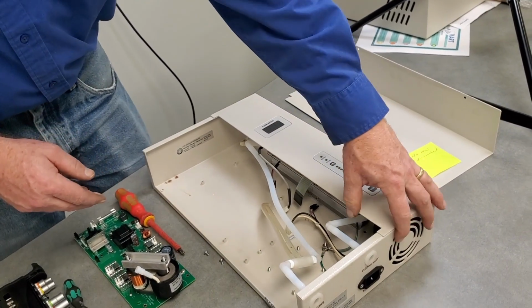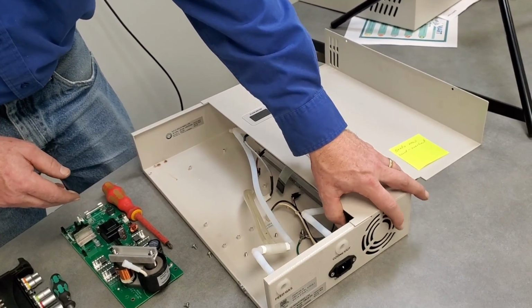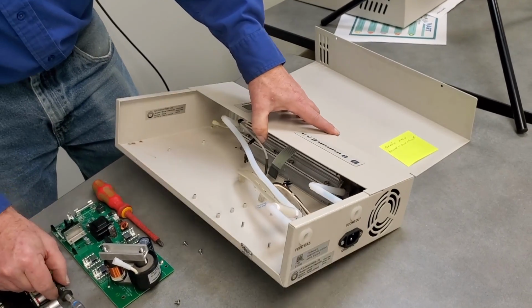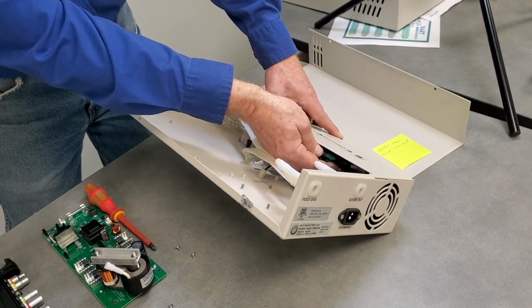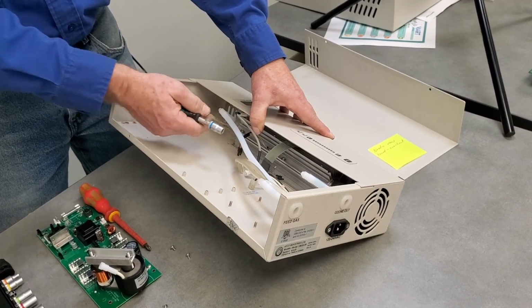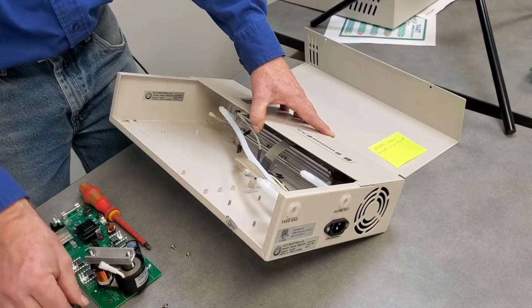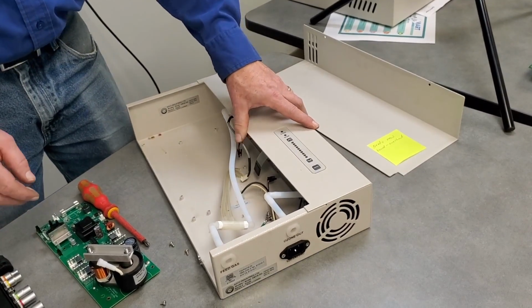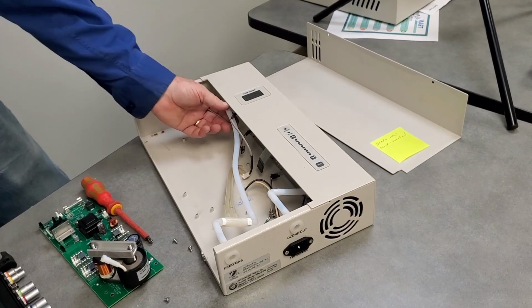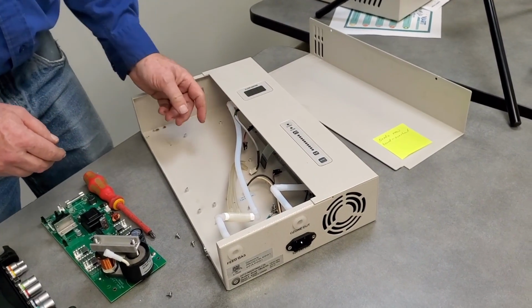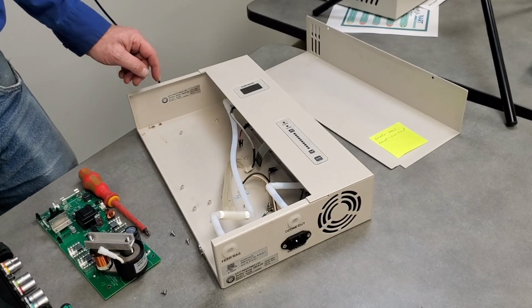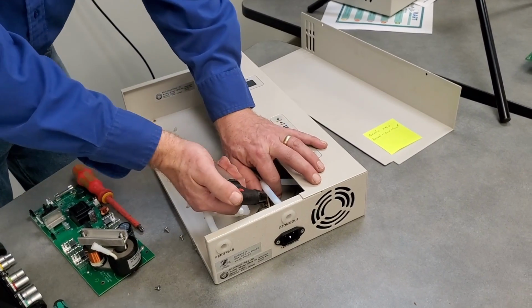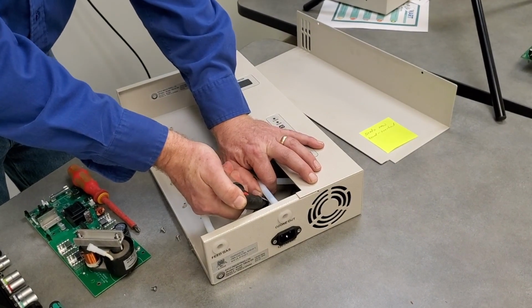The fan is the other issue. The fan was not working. These fans are not so easy to get out because there's a nut way in the back on the top, and it works better to just take the whole cell out. So I'm going to do that while we're at it here. So to take the cell out, we need to heat up these fittings. We'll just do this one right here.